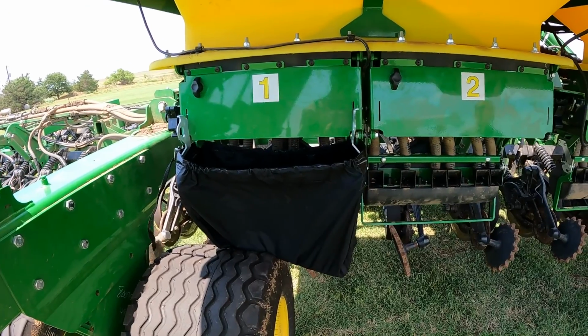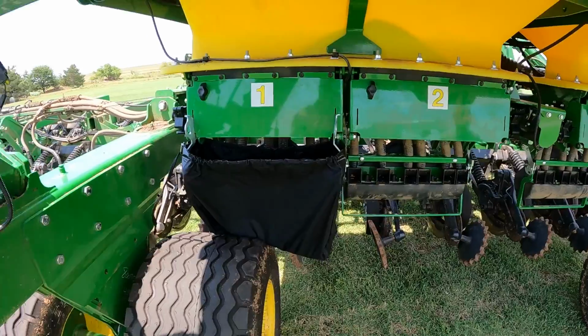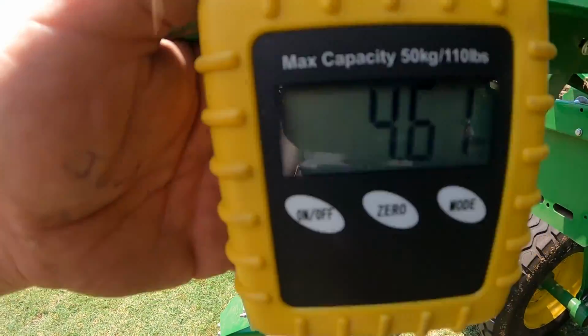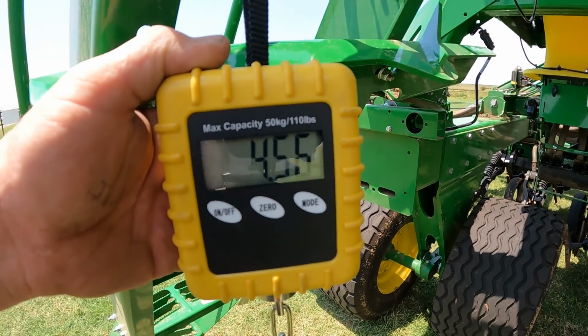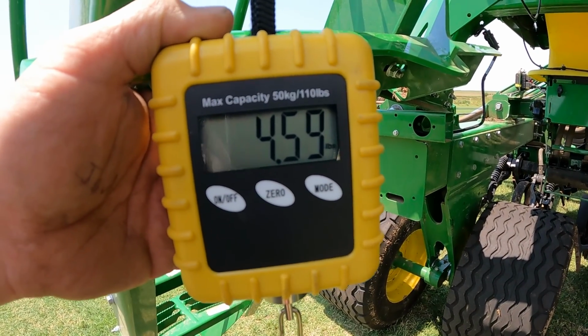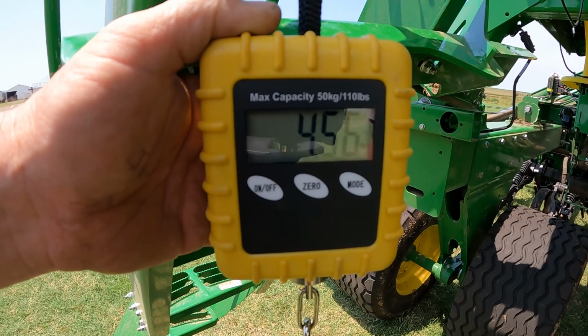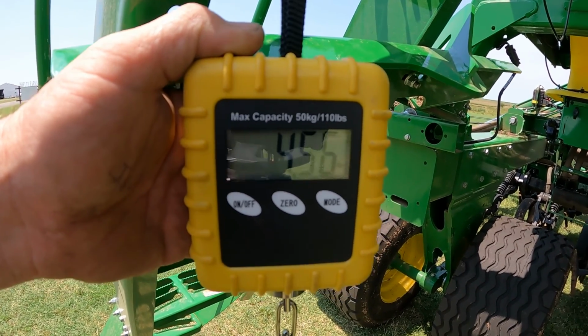Meter stopped turning, so we're going to pull our bag and weigh that product real quick. That product weight, you can see, is 4.59 pounds. We'll key that into the display, and that'll give us a true cal number for that far left meter: 4.56 pounds.